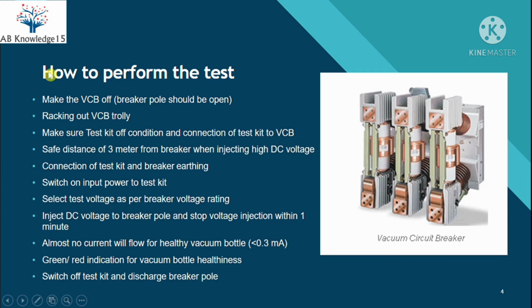Now we will discuss how to perform this test. First of all, the VCB breaker whose vacuum bottles you want to test should be in off condition. The breaker pole of that VCB should be in open condition. Secondly, take the VCB trolley totally out of the switchgear panel so that you can see the VCB breaker from the rear side, like this. This is the rear view of the VCB breaker. Here you can see that behind the breaker there are 3 vacuum bottles.